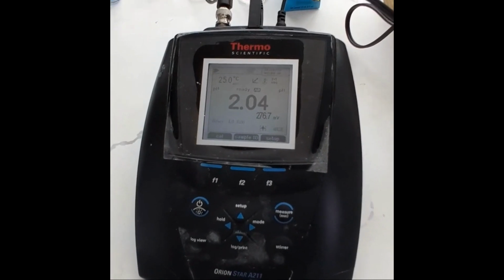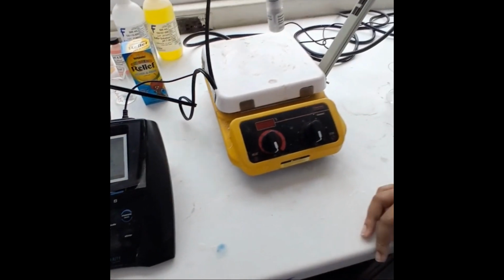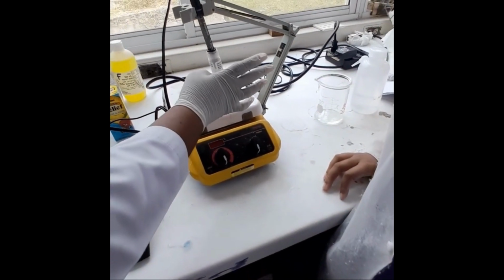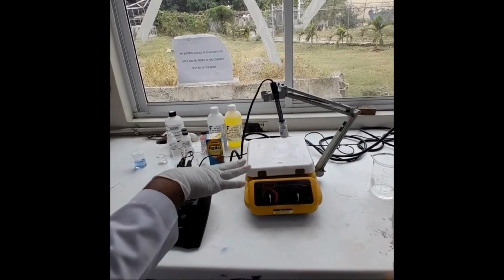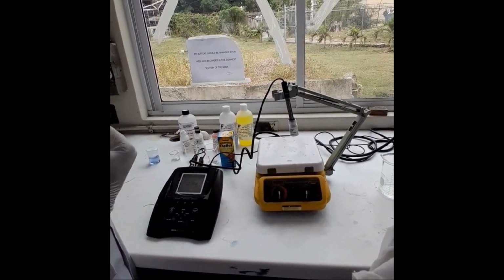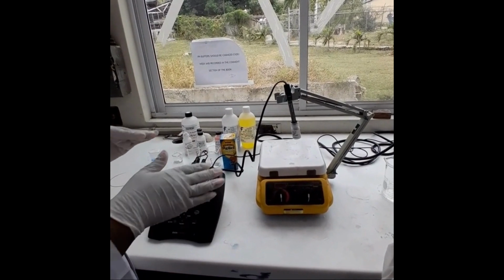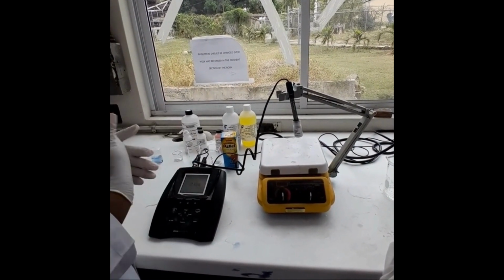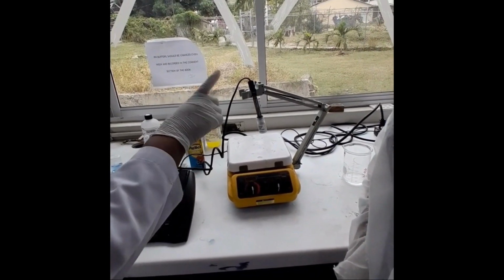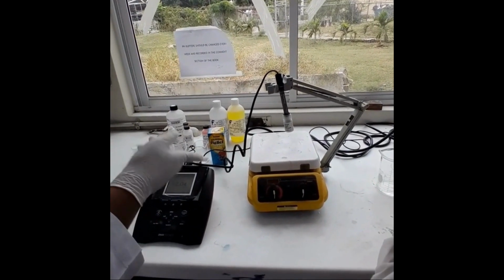The next part of the pH meter is the probe, which I've shown you before. It is stored in a solution. The solution for the probe is potassium chloride, so ensure anytime the pH probe is not in a solution or is not being used, it is washed with distilled water and returned to this storage solution.